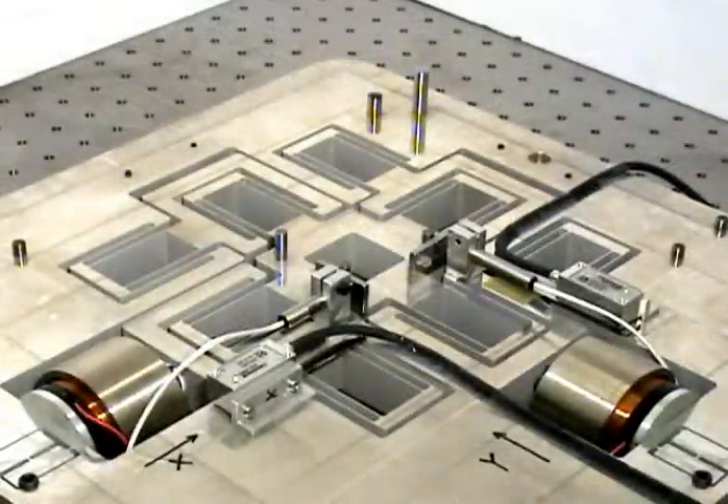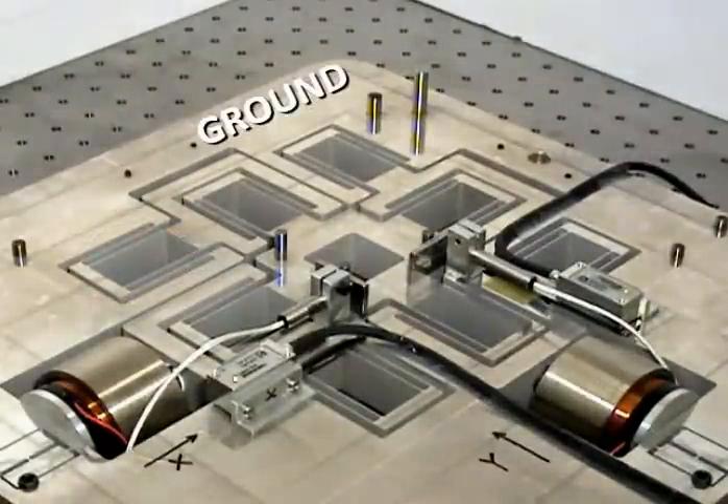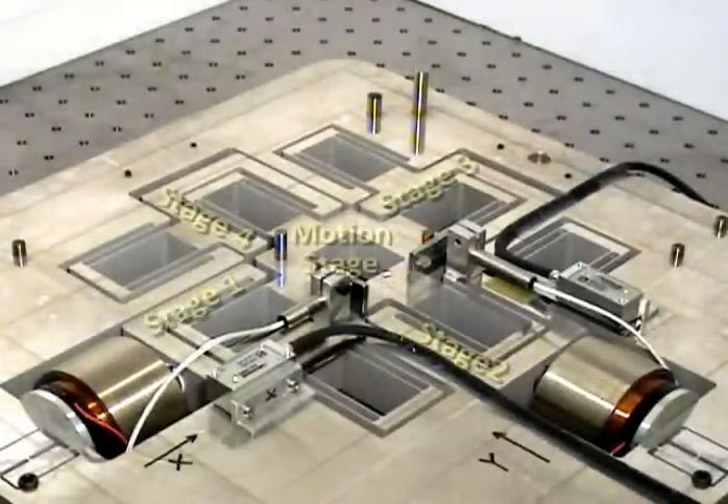Let us now go over all the components of this system. Please note the X and Y directions as marked by these axes. At the heart of the XY nanopositioner is a novel flexure bearing design. This flexure bearing makes use of a highly symmetric geometry that is generated by means of a systematic layout of double parallelogram flexure building blocks. The outer frame provides the ground for the flexure bearing and the entire nanopositioning system. At the center is the motion stage that moves along the X and Y directions.